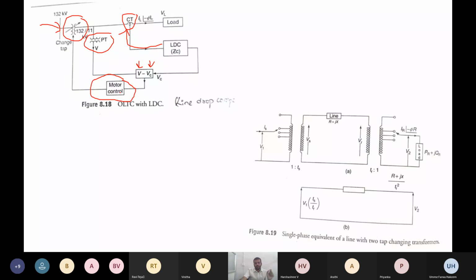Okay. So the signal to this motor control will be sent by our LDC. LDC is our ZC. So LDC will give the signal into our system by measuring the voltage difference between V and VC. So this VC is the voltage that is measured across the ZC components, and V is our actual voltage. So the actual voltage, that is 11 kV, you can observe. Okay. So this is our complete operation using OLTC and LDC.